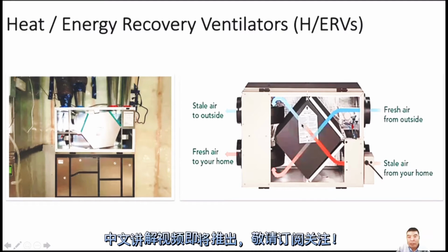But let's look at this picture here. We should know the principle of the HRV or ERV. There are normally four ports around the HRV, sometimes on the side, sometimes on the top. It doesn't matter which way. You can see a sticker or mark around each port that tells you what the port is used for.